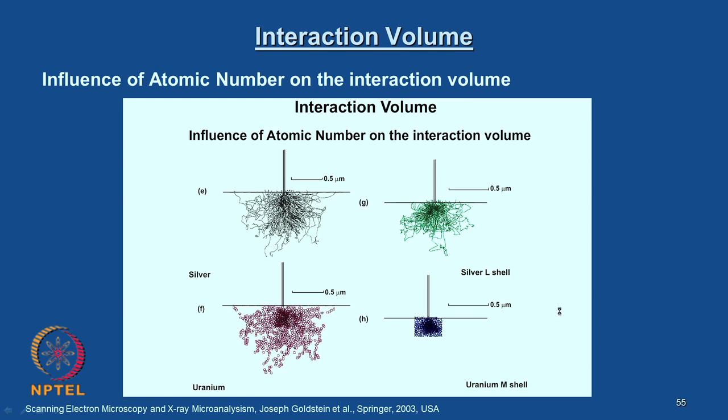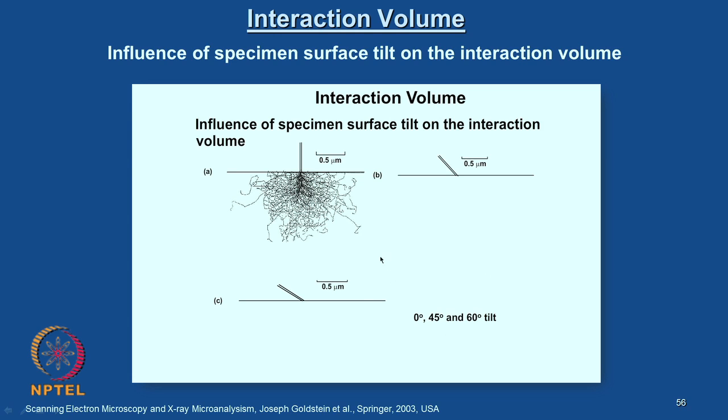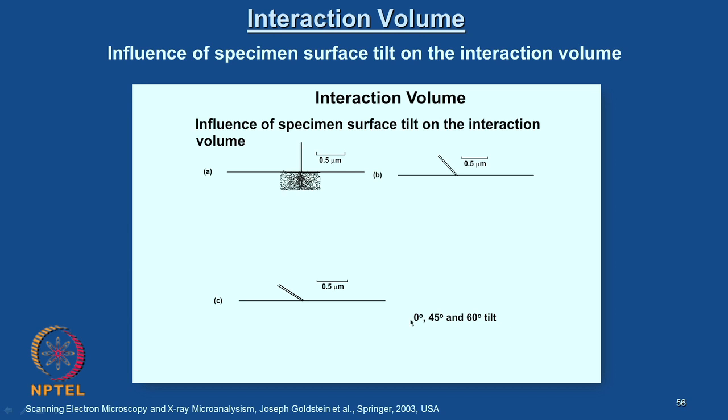It is not just atomic number — there is also an influence of specimen surface tilt on the interaction volume. In SEM operation, the specimen is tilted to the required angle in order to collect the appropriate signals in large quantity. The specimen tilt will have some influence on the interaction volume, and hence the output — whether it is secondary electrons or backscattered electrons — which eventually decides image quality and resolution. The simulation shown here is for 0-degree tilt, 45-degree tilt, and 60-degree tilt. A higher tilting angle also slightly reduces the interaction volume.